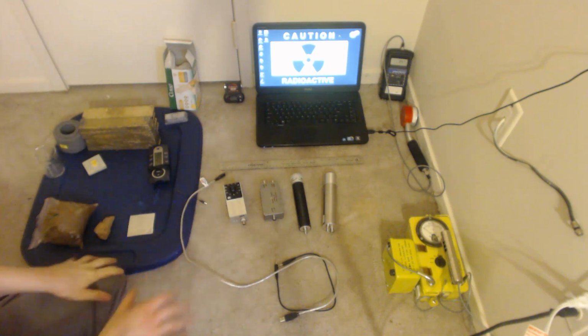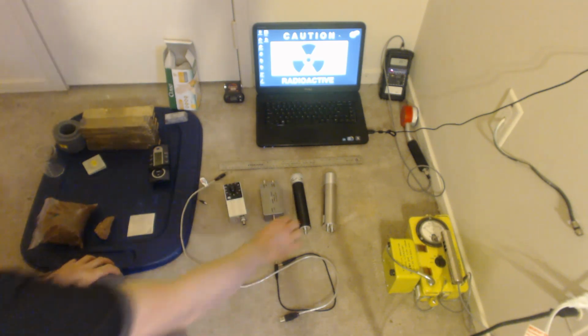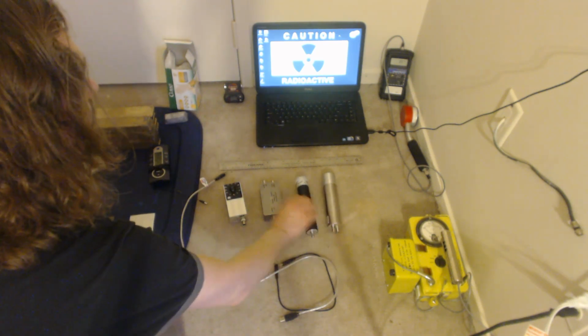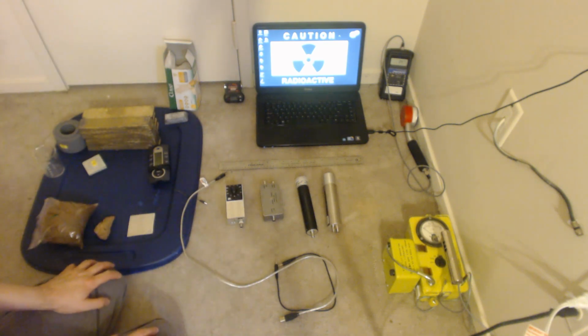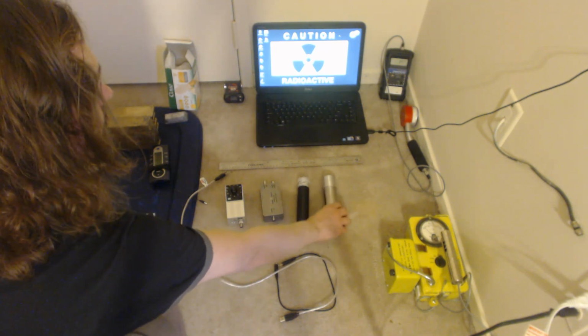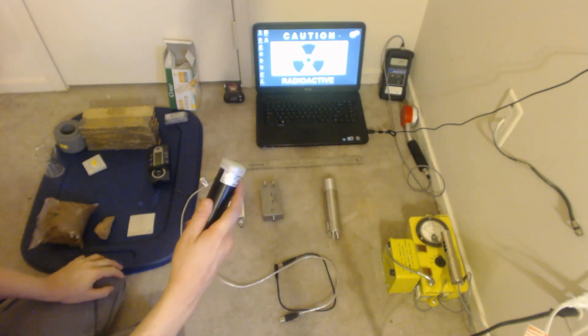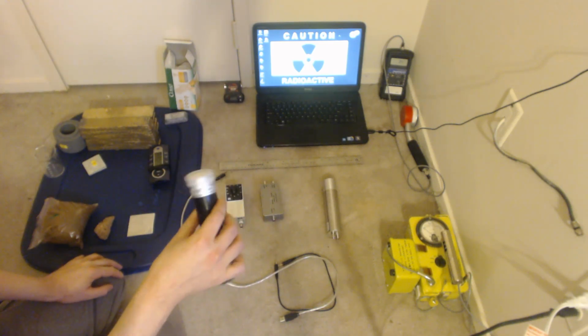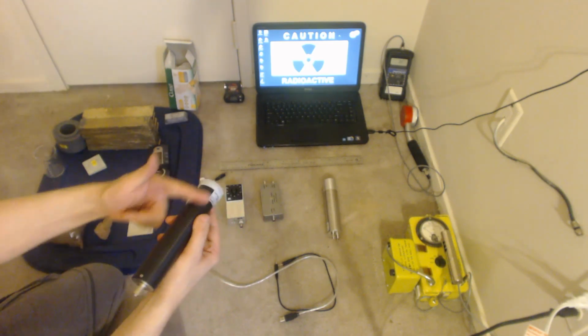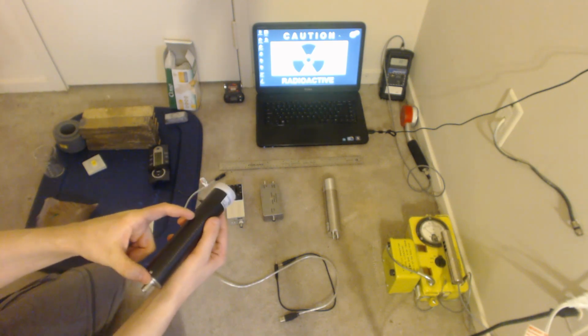So let's talk quickly about detectors. First off, detectors like these guys are crystal detectors. You are not going to be using a semiconductor detector with something like this, like a high purity germanium detector. Besides, if you spend the $10,000 to $20,000 for one of those, you probably already have all the rest of your equipment anyway. These detectors are crystal detectors. They have a crystal inside of them. The crystal is excited by gamma rays, which does that whole effect I explained a few minutes ago with photomultiplier tube built into them.